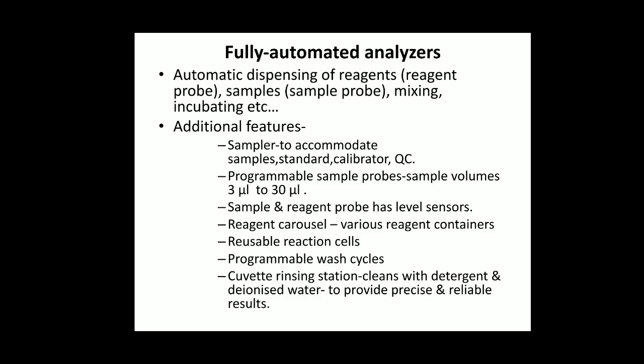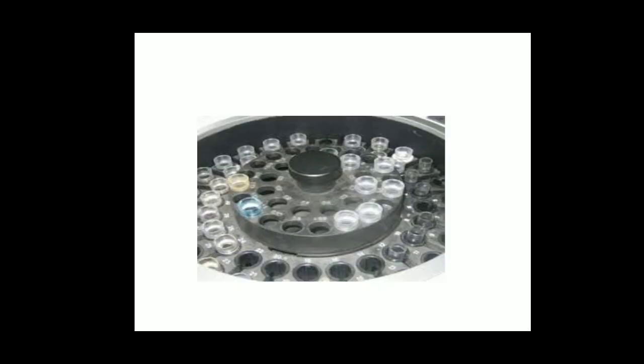Reusable reaction cells: once the cuvettes are used, they are washed, disinfected, cleaned properly, and reused. A cuvette rinsing station is there to rinse the cuvettes. If the cuvette is not rinsed properly, it might interfere with the test report of the next patient.